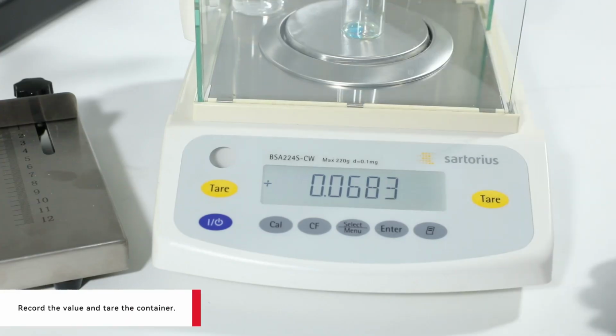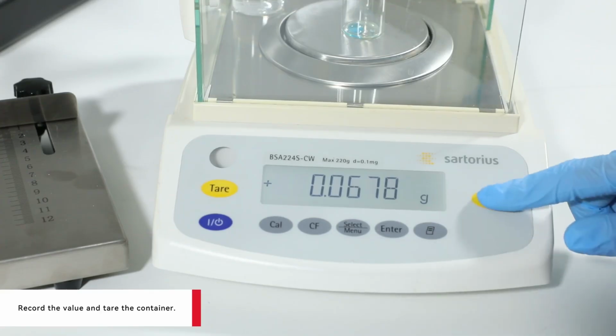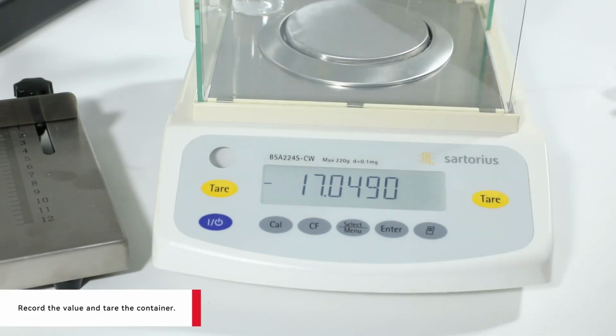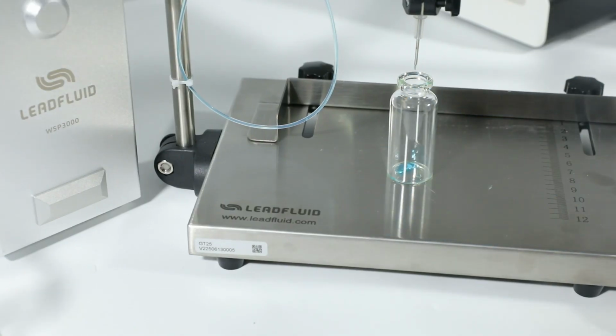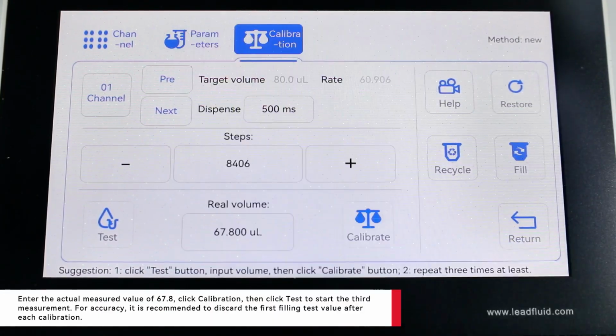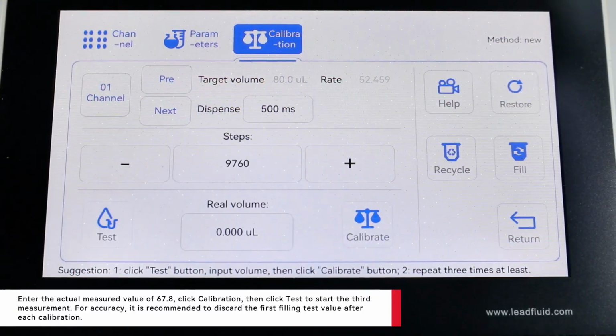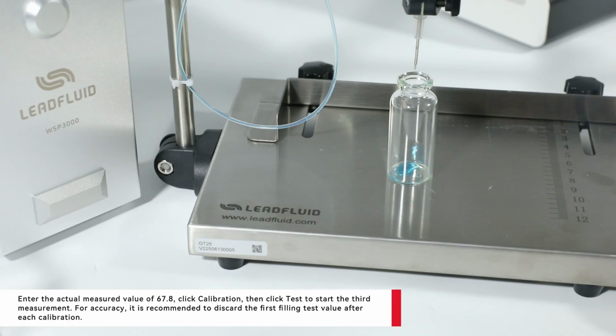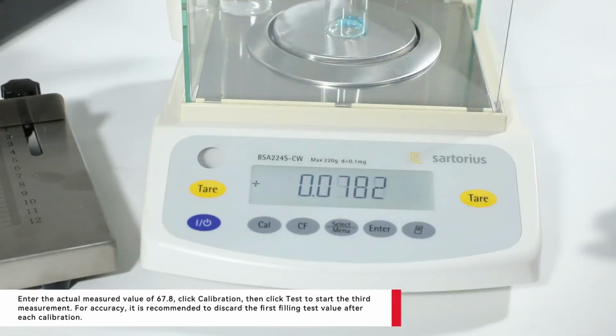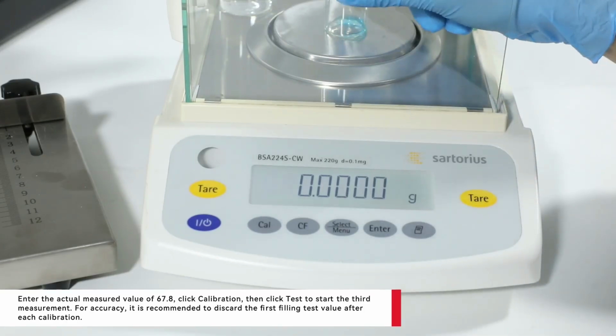Record the value and tare the container. Enter the actual measured value of 67.8. Click Calibration, then click Test to start the third measurement. For accuracy, it is recommended to discard the first filling test value after each calibration.